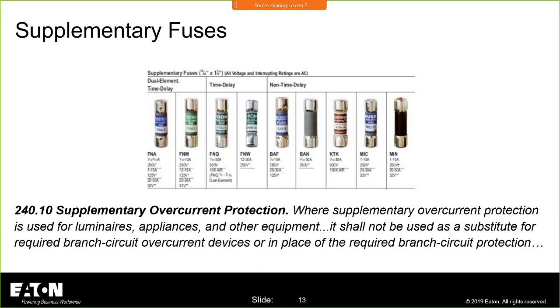This is where supplementary overcurrent protection in things like luminaires and appliances comes in. You'll see these inside of equipment and any type of little panels and whatnot. You'll see them in your HVAC unit. I think it was last year, I had to replace a fuse. We had a huge event outside, a lot of lightning and whatnot, and I had a surge that opened up a fuse. So I had to replace one of those, but that would be a supplementary fuse.